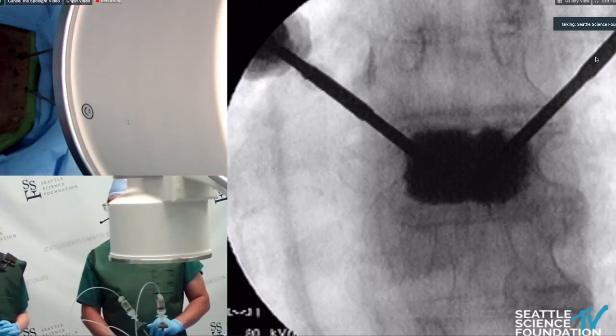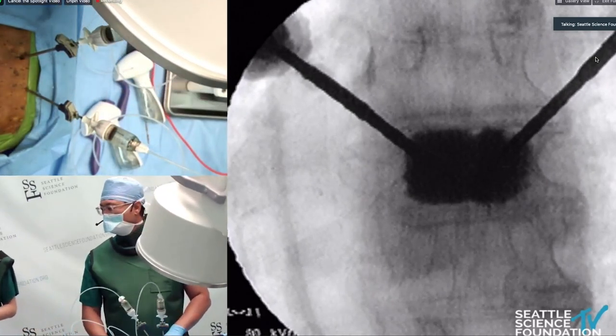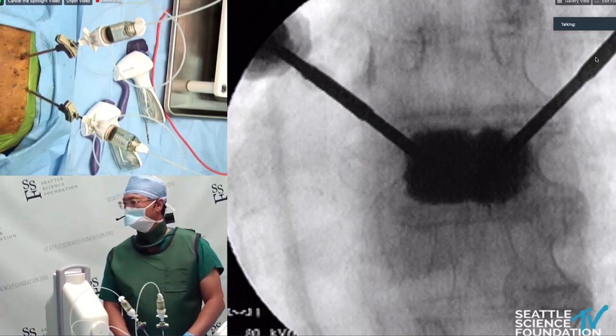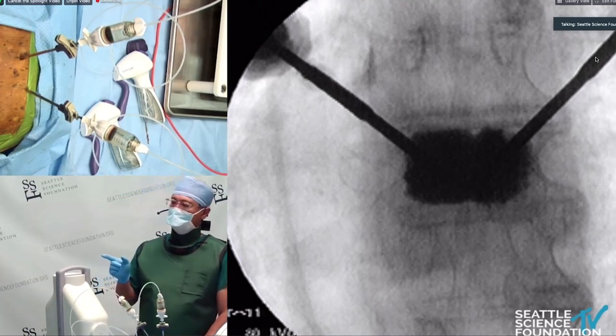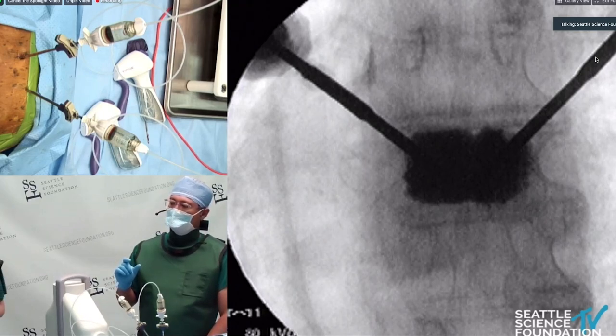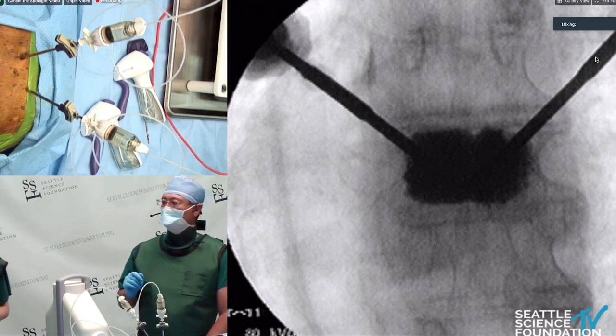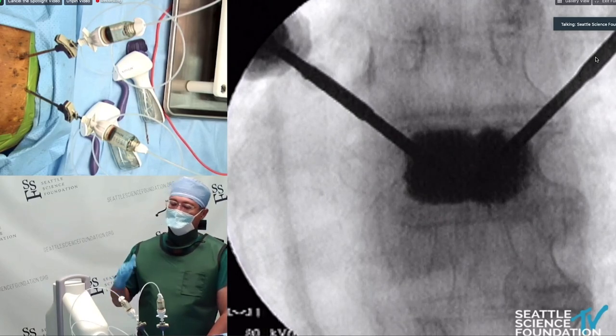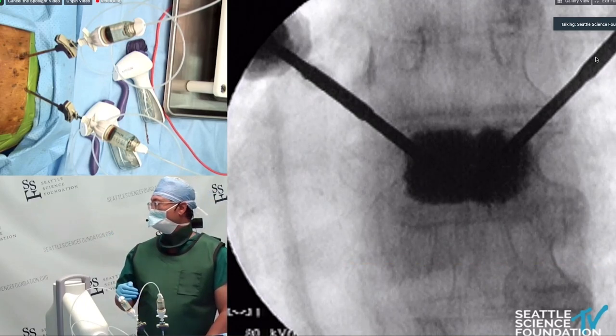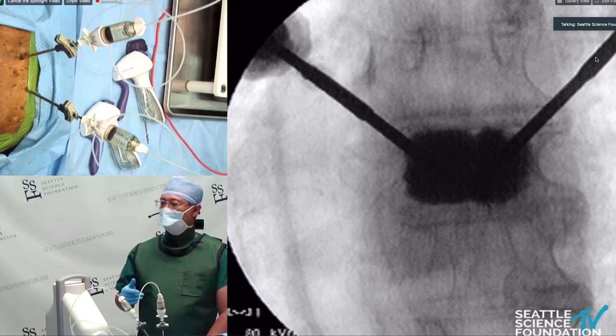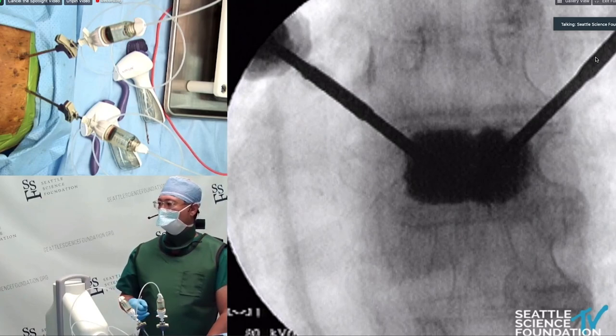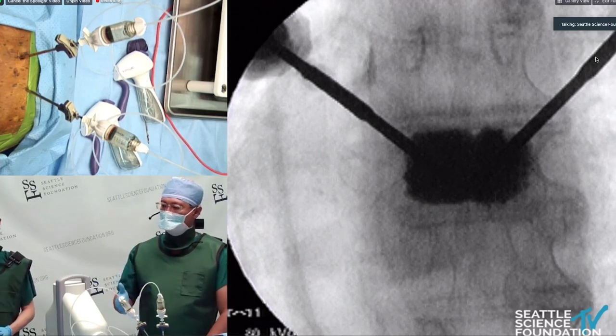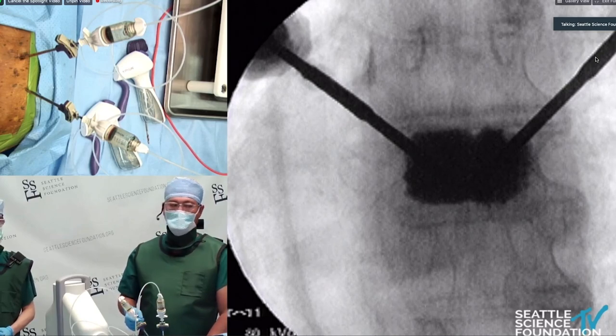To summarize the Osteocool technology: the machine measures the proximal tip of the probe, which is at 70 degrees Celsius; the mid portion of the active part of the probe is at 95 degrees Celsius; and the distal tip is at 70 degrees Celsius. Depending on what size probe is used determines the size of the ellipsoid lesion — its width and length. Together, two probes provide an even larger lesion to cover that vertebral body adequately.